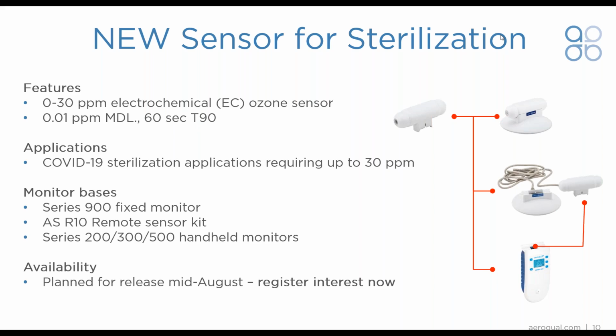They want to ensure ozone levels are retained and maintained during that process. In response, Aeroqual is going to release in August a 0 to 30 ppm EC sensor that can be used on our fixed monitor base, the AS R10 Remote sensor kit, which allows you to put the sensor into a room while having the monitor outside, connecting into our handheld monitor shown at the bottom of the slide.